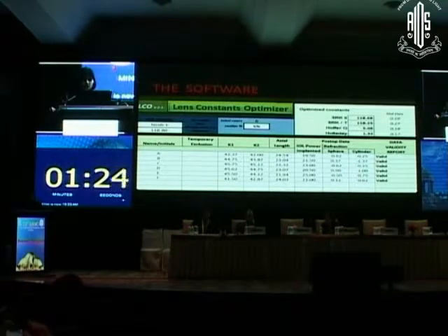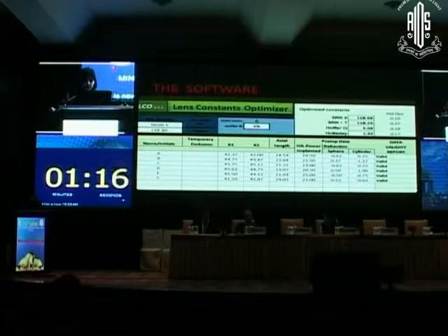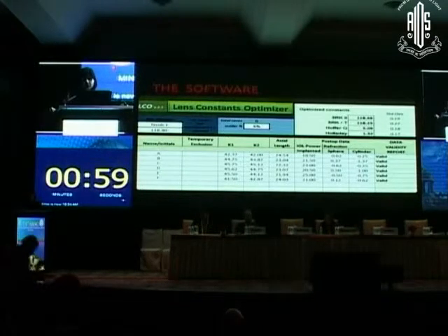In case you want to use the SRK II formula, it's telling me that after these 6 cases, my A constant should not be 118.8, it should be 118.68. If I'm using SRK/T, from next time I use a Technis, I should be using a constant of 118.25. And Hoffer Q and Holladay. By Holladay, I mean Holladay 1. These are the 4 common formulas that we use, and it will give us the optimized constants for these 4 formulas.